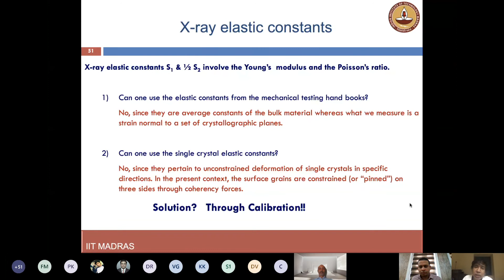And how do we do that? You need to calibrate. Many times, when we deal with standard materials, the X-ray elastic constants are already available in the database. The software will have it. If it is not the case, then you need to calibrate and do it. For example, if you're working on an entirely new material which is not in the database, then you need to calibrate and get the X-ray elastic constants.